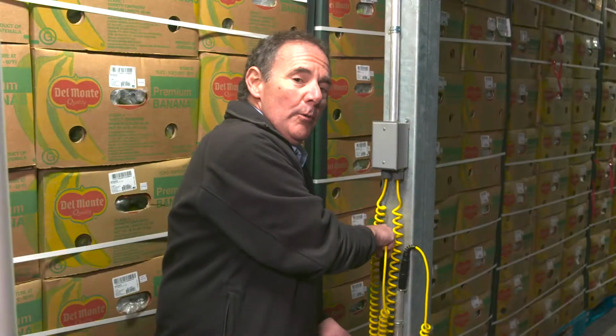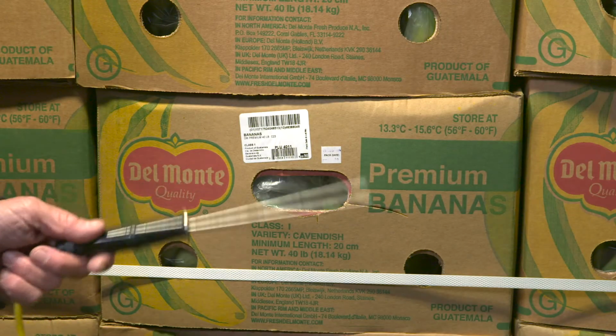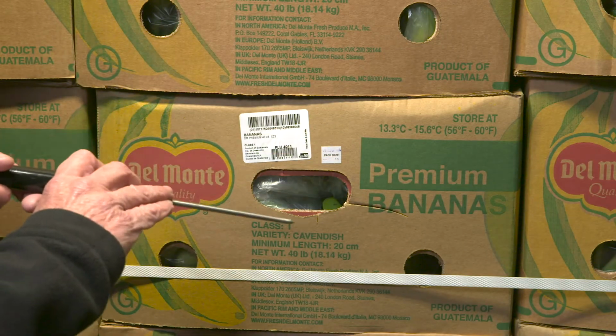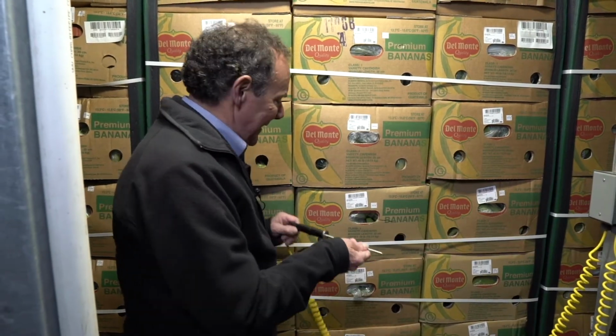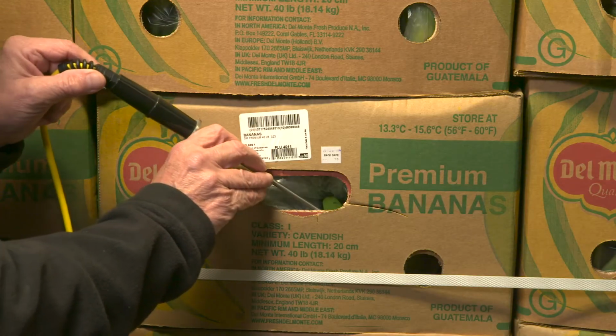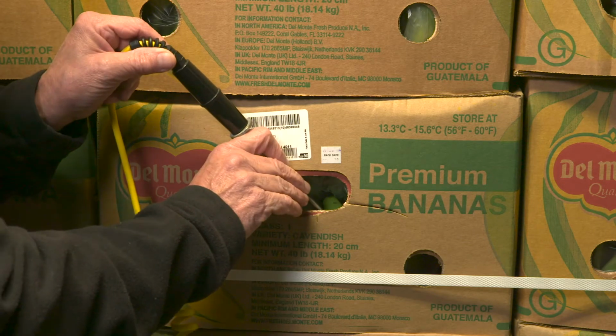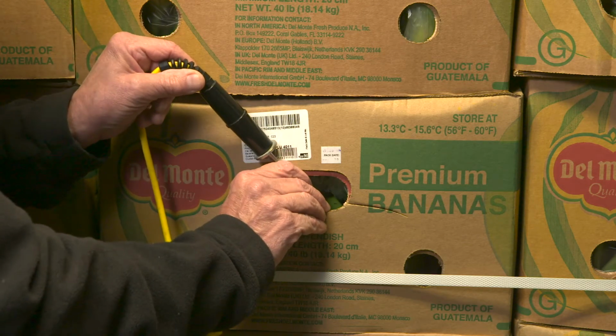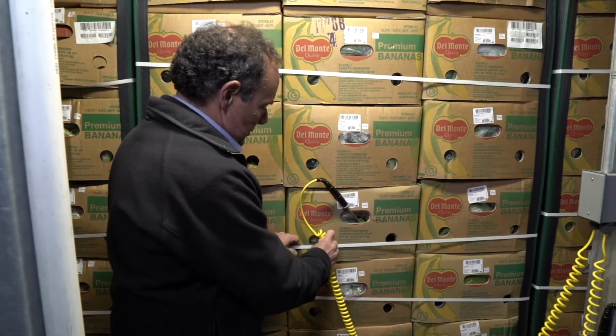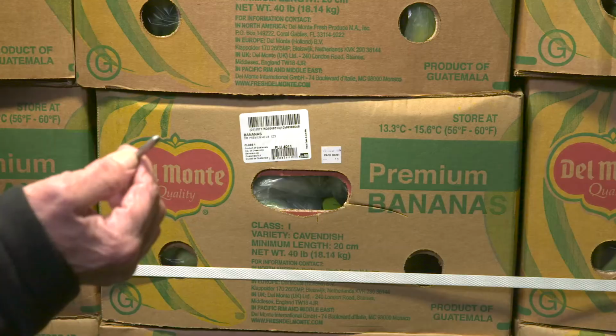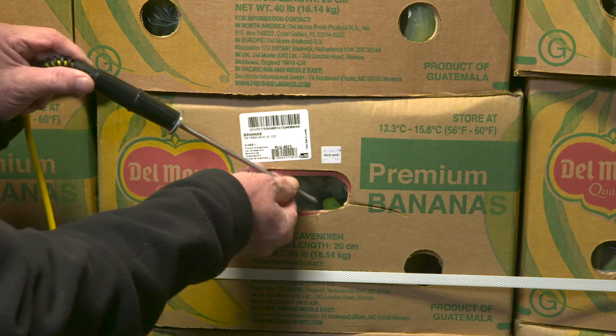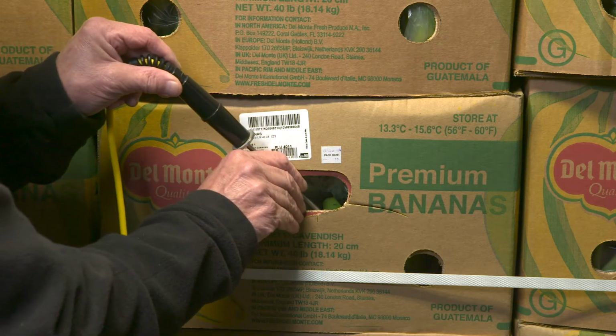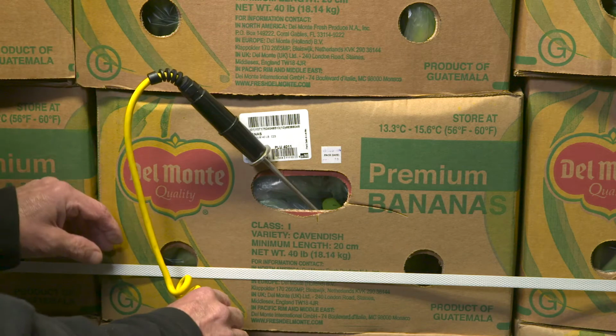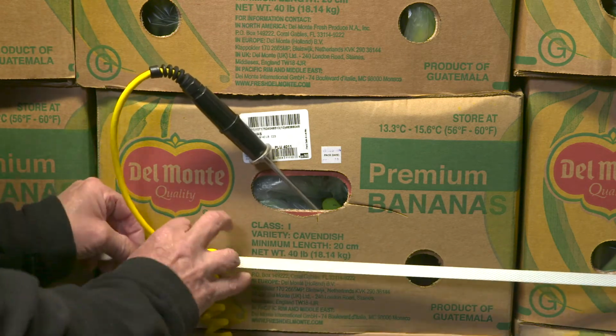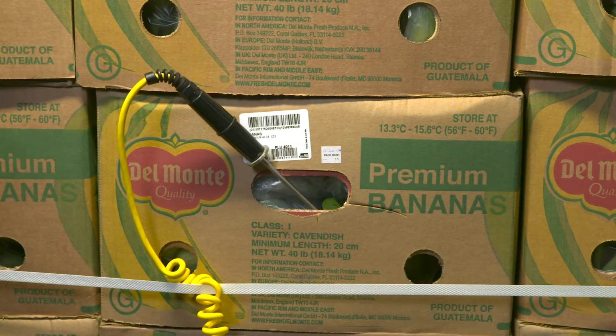Most important of all are the pulp probes, located on the bottom tier near the rear of the room. Pulp probes monitor the actual pulp temperature of the fruit. In order to insert the probe properly, take the probe and place it 1 inch into the center of the pulp of the fruit as such, and you're done. When inserting the probe into the fruit, make sure the tip of the probe is facing toward the door. This way, the probe won't be ripped out of the socket if someone pulls the pallet out of the room before the probe is removed.